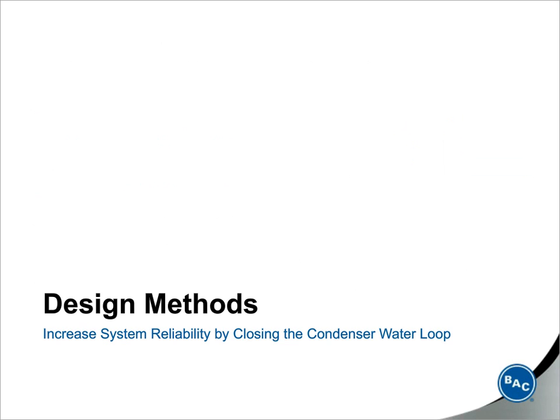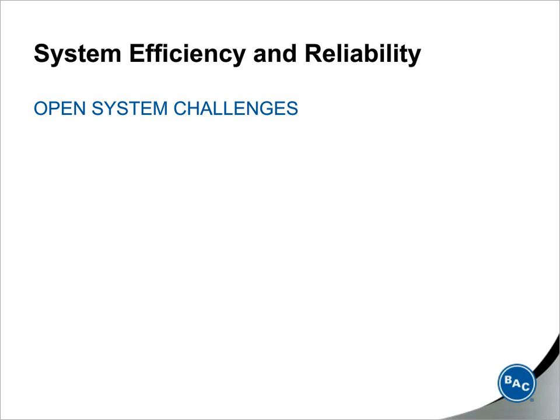So we've now gone through methods to reduce energy usage and total cost of ownership. Now we're going to discuss a way that can really increase overall system reliability by closing the condenser water loop. Building owners spend a lot of money on these systems. They're very expensive, and owners expect to maintain peak performance for a very long time. By closing the condenser water loop, you're essentially protecting the chiller or heat pump from dirt and debris. And since the chiller consumes the most system energy, it really pays to protect the chiller from fouling, which can ultimately lead to some really big efficiency losses.